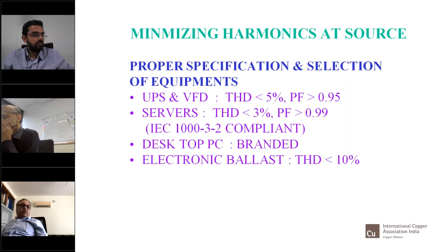Electronic ballasts also generate around 33 to 40% harmonics, the early versions and the cheap versions. Later the highest standard came for electronic ballasts, and ballasts became available with less than 10%. Many old installations have not been changed to LED. Many offices still have CFL lamps and T5 tubes where these ballasts are used. If somebody is in the process of changing the ballast or the fittings, please ensure that you buy ballasts with less than 10% harmonics.